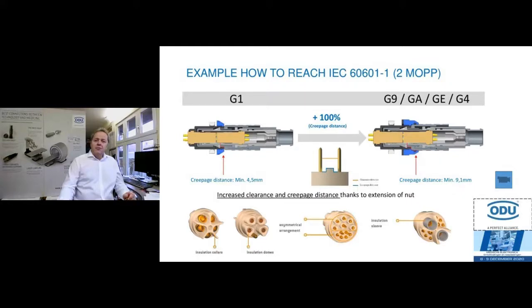You see there's a red marker here, and the creepage distance is the distance between the last pin inside the connector and the outside body - shown by this red line which goes around the housing of the plug and receptacle. This distance is right now, on the G1, only 4.5 millimeters. To be conformant with IEC 60601-1, you need 8 millimeters, so 4.5 is not enough.